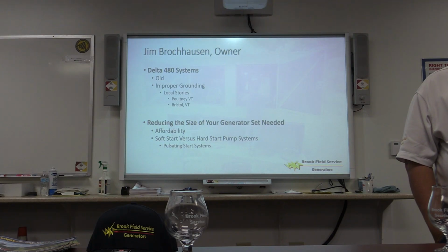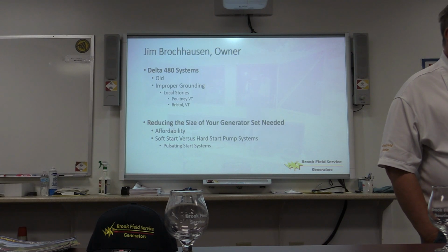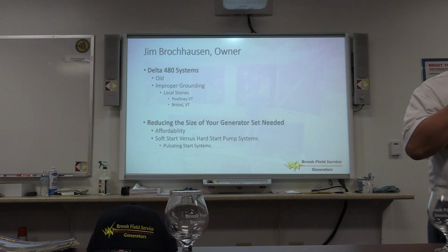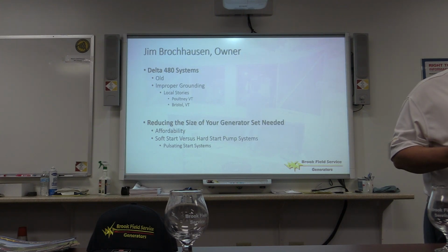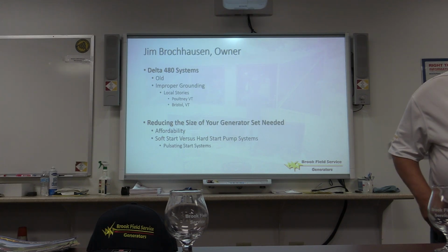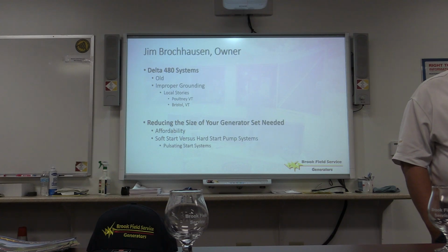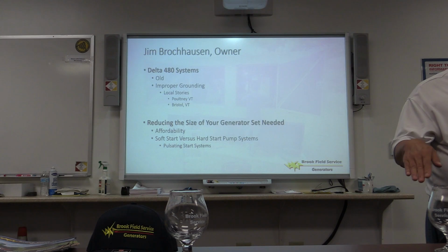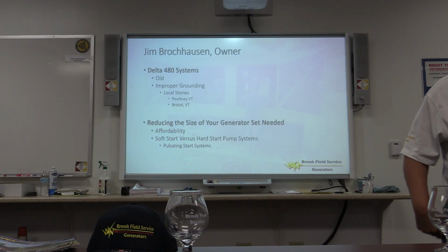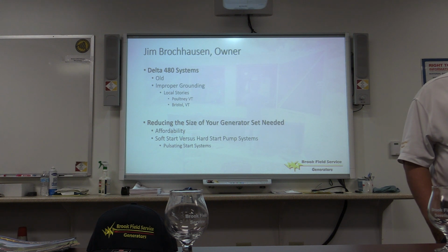So many of the plants that we come across were built in the 70s. And we had 2 instances over the last year where they have a 480 delta system, but it's the oldest type of system, so there's no neutral coming from the utility. That sets up a potential problem in that if there's a short to ground, it's not detected.